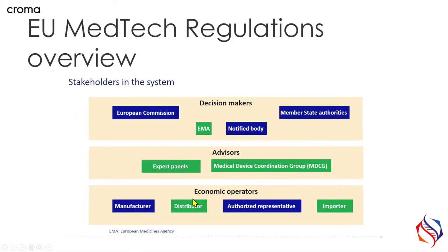So typically, as a manufacturer here in Austria, we have one notified body, which is located in Germany, because we are free to choose a notified body in the European Union. We're not bound to our national territory barriers. So this is the notified body we deal with on a yearly basis for supervision audits and for granting CE marking. And then any member state authorities where we distribute our products, for example in Austria, Germany or Italy, can in the same way inspect our dossier and our file in case they have any requirements in the post-market area or any questions on the products, on the labelings, or on our advertisement activities.